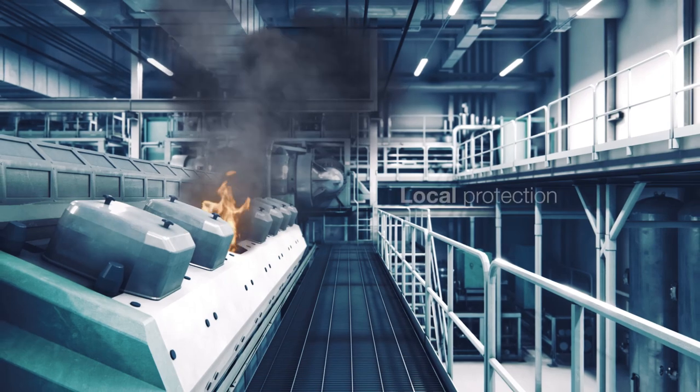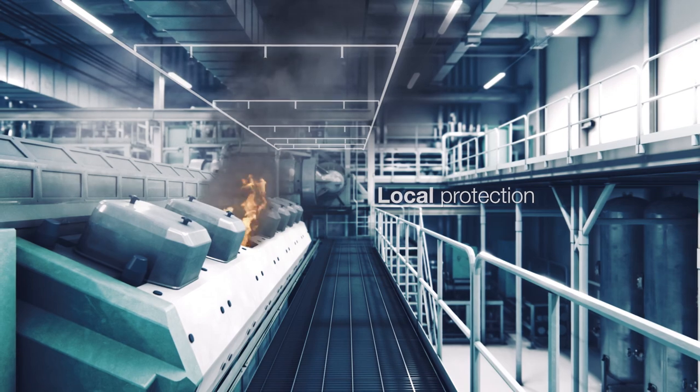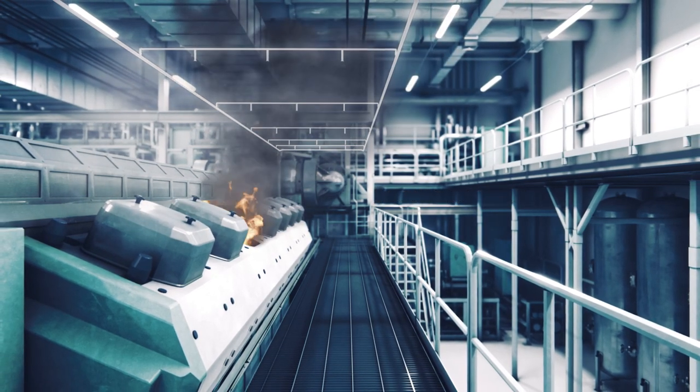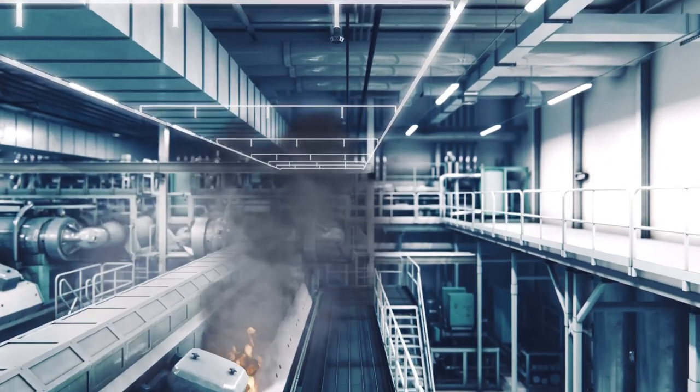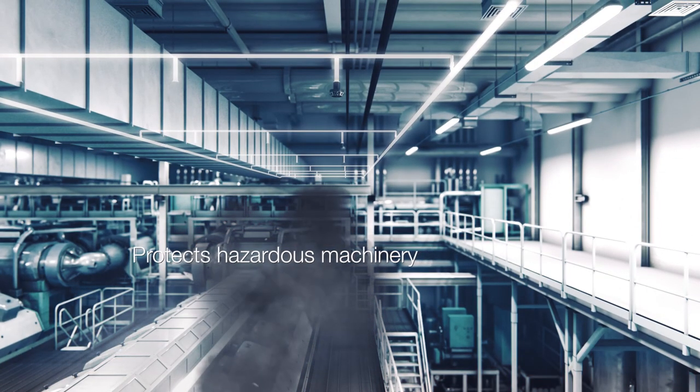The local protection system is designed to protect most hazardous machinery on board, such as engines, purifiers and boilers. Hi-Fog spray heads are divided into sections in a way that each protected object has its own section valve.